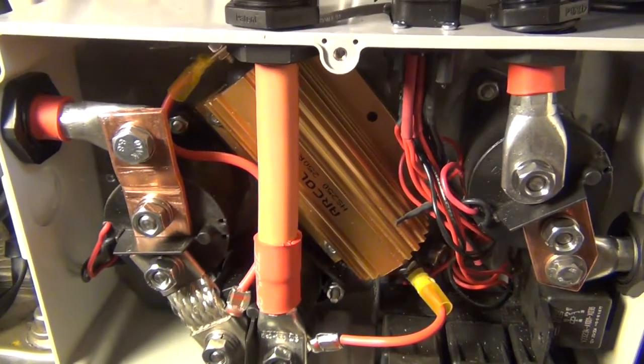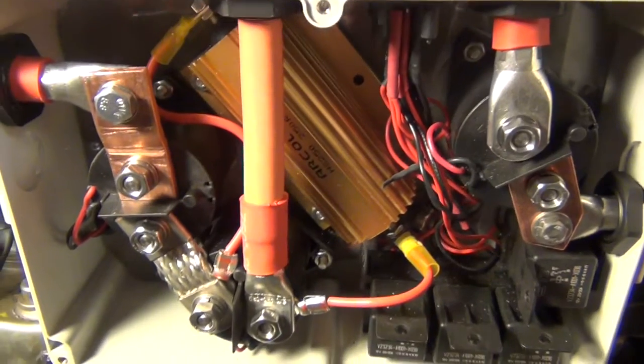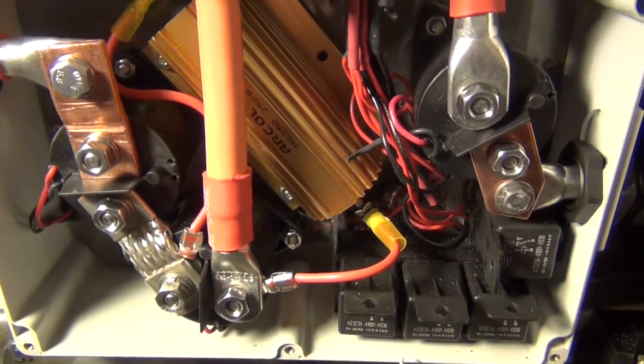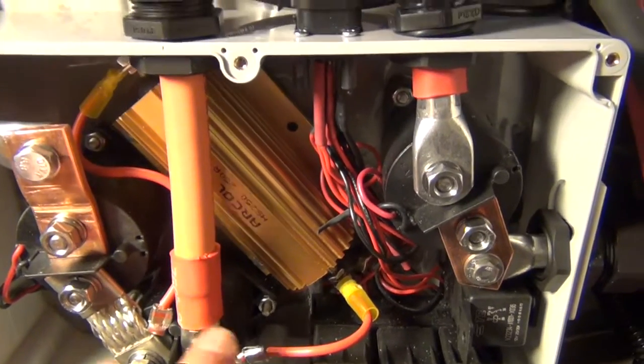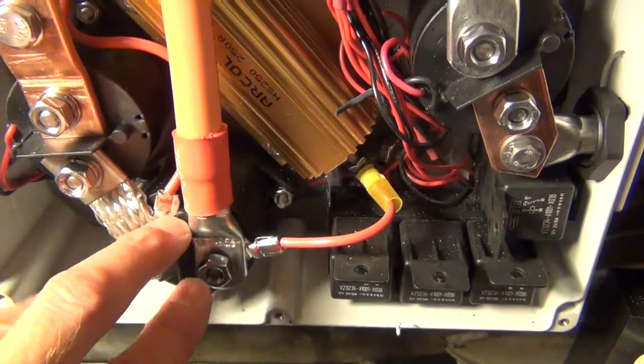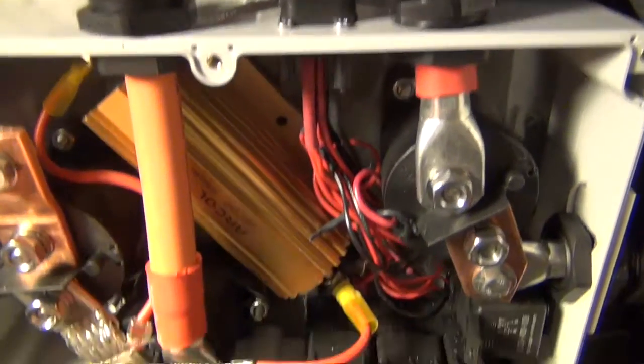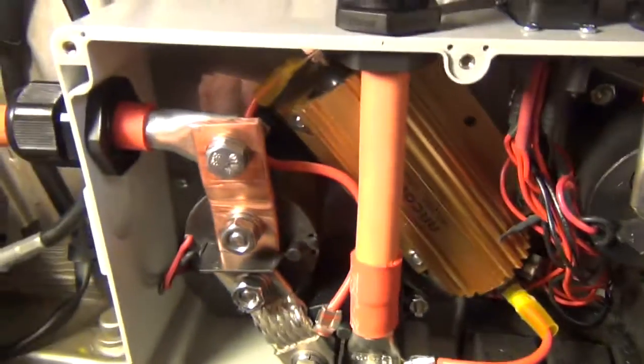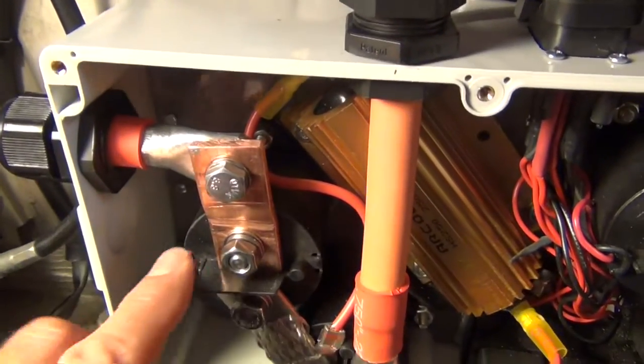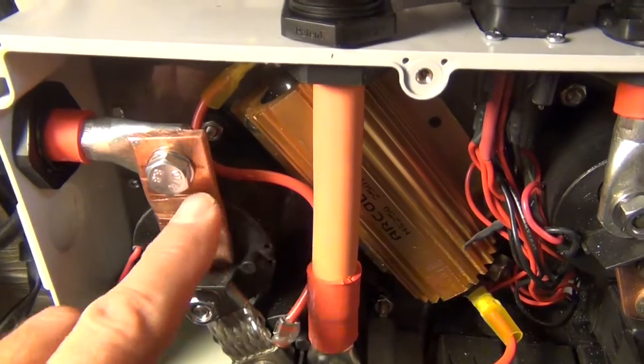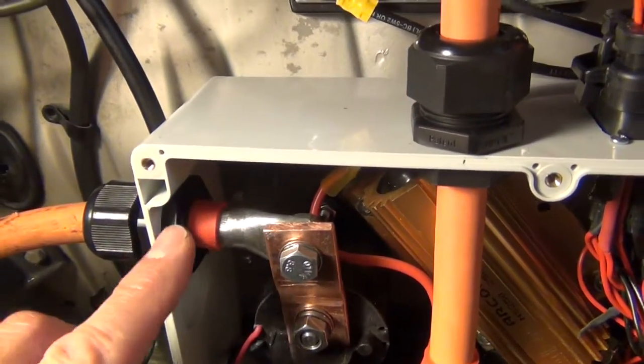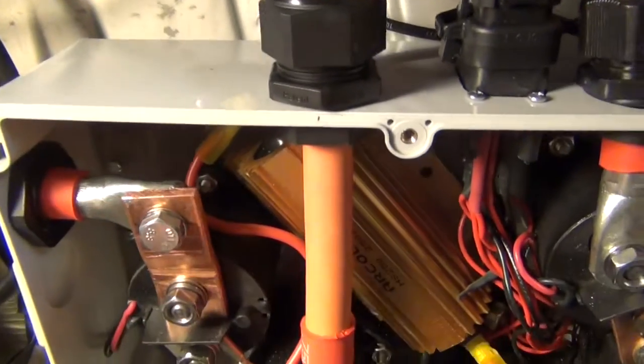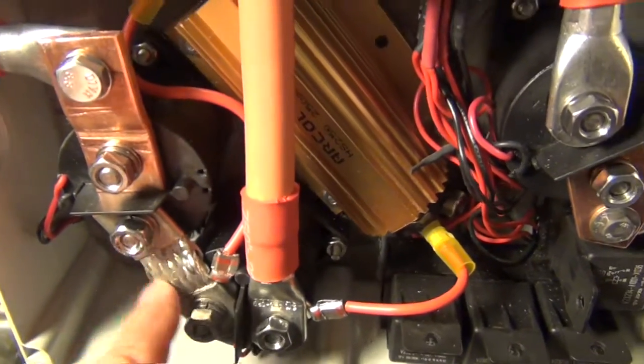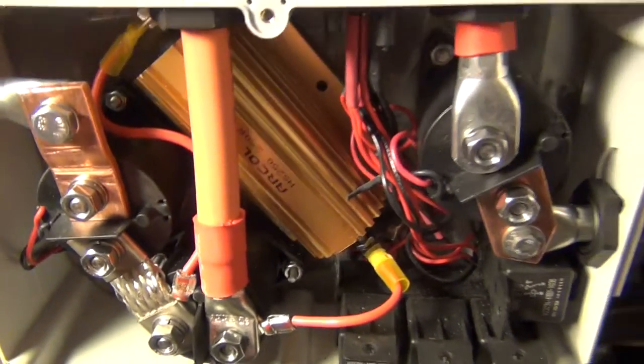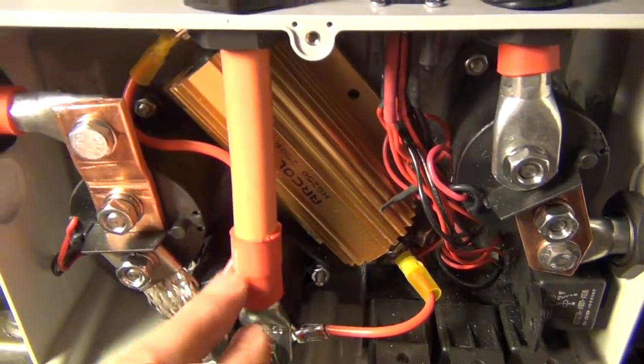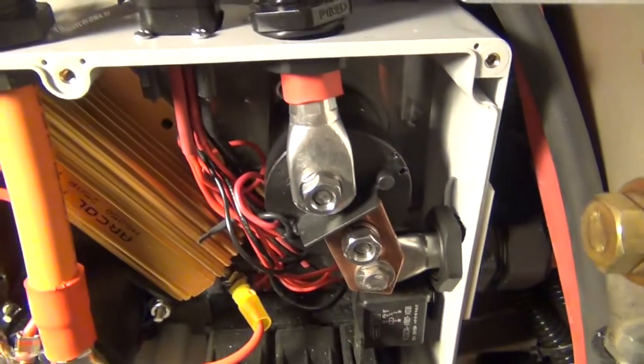One of the issues with this contactor box - it's great, you can see stuff pretty well - but one of the problems is you don't have enough distance between a contactor and the gland nut for a cable to take up some difference. The height of these is too tall for the side of the box. So what I had to do in this case is make up a copper plate with a little bend in it to take up the offset, so you can come through the side and make contact to the contactor. There's even a strap between them. So this is the pre-charge contactor, then the main contactor, and then the main contactor for the low side.